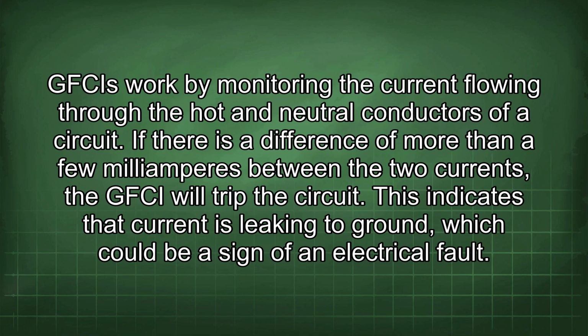GFCIs work by monitoring the current flowing through the hot and neutral conductors of a circuit. If there is a difference of more than a few milliamperes between the two currents, the GFCI will trip the circuit. This indicates that current is leaking to ground, which could be a sign of an electrical fault.